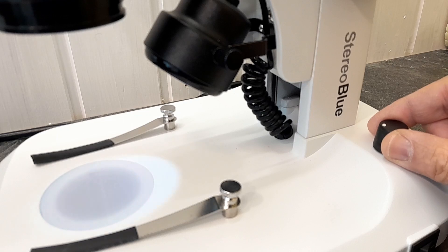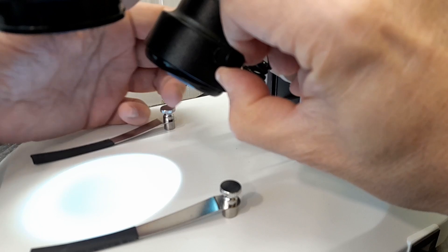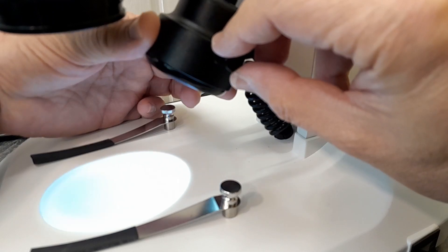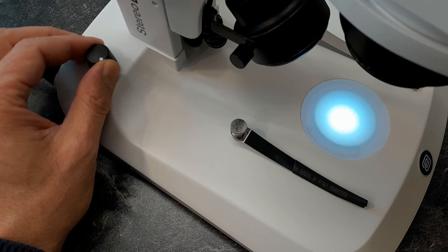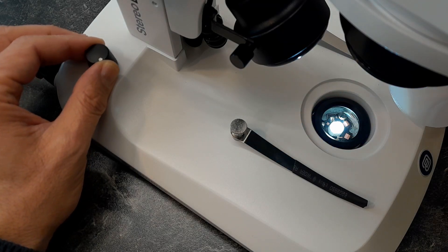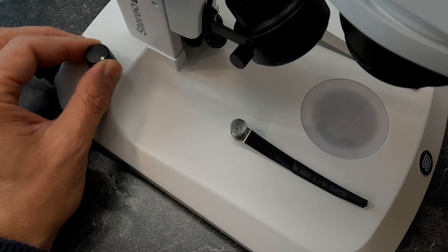For lighting, there are two adjustable LED lamps: one on top and one from below. Both can be controlled separately and brightness is adjusted by turning a button. The top lamp's angle can also be adjusted and locked into position with screws. On the bottom there is a diffuser glass stage which ensures even illumination, and depending on the specimen you can choose the combination of both lamps. Microscope slides can also be observed using the bottom lamp.